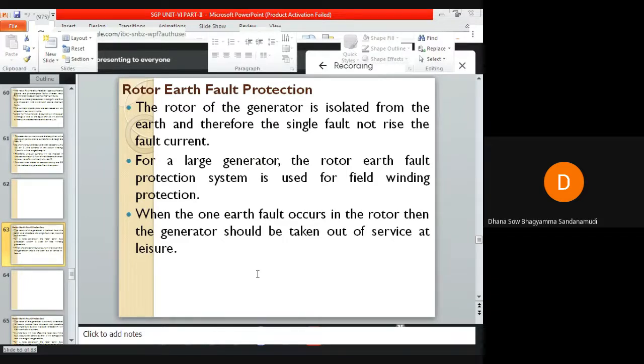Even if insulation breakdown occurs in the rotor windings, there will not be any leakage of current if a single fault occurs. So a single fault due to insulation breakdown of the rotor windings will not affect the rotor. But if the fault occurs and continues for a longer period of time, it will damage the field winding of the generator. So for large generators, a rotor earth fault protection system is used for protecting the field windings.